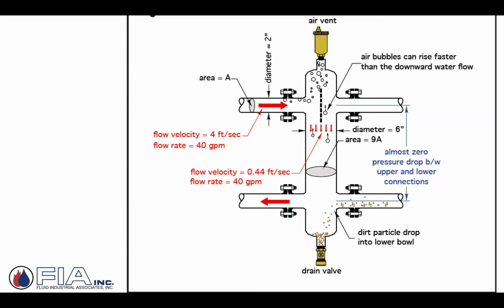Just a real quick cutaway, the way it works, again, back to what pipe diameter and then what's the diameter of the shell. And it's very engineered, it's very specific. So that the 4.5 feet per second velocity as it enters this diameter, it drops it to just basically less than 1/2 foot per second. But it's a low pressure drop, works well for primary, secondary connections, works well to separate air bubbles from the pumped flow, as well as potentially a place to gather dirt separation and then blow it down through your blowdown valve.